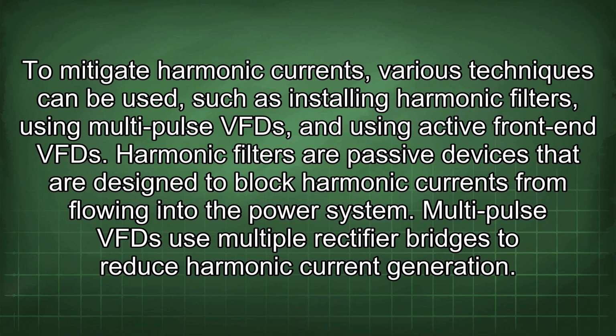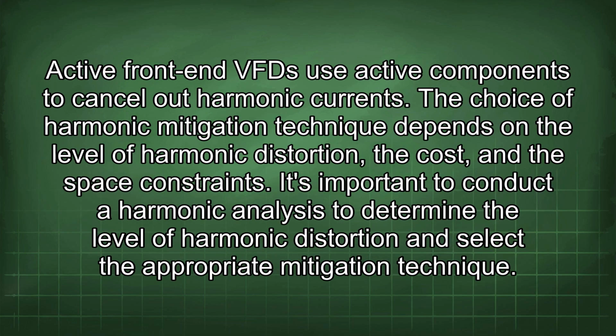To mitigate harmonic currents, various techniques can be used, such as installing harmonic filters, using multi-pulse VFD, and using active front-end VFD. Harmonic filters are passive devices that are designed to block harmonic currents from flowing into the power system. Multi-pulse VFD use multiple rectifier bridges to reduce harmonic current generation. Active front-end VFD use active components to cancel out harmonic currents. The choice of harmonic mitigation technique depends on the level of harmonic distortion, the cost, and the space constraints.